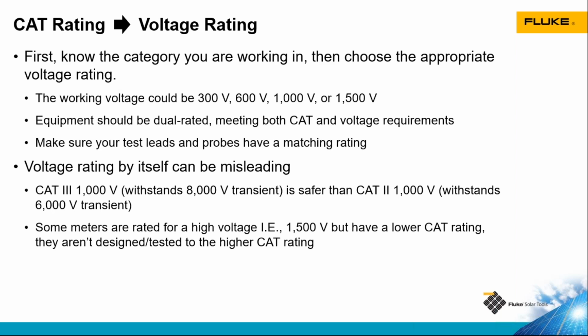And it's important to know that some meters on the market will be designed to test to a certain voltage, say 1,500 volts or even 2,000 volts. But when you look at the category and voltage rating, it's much less. I've seen 2,000 volt test tools that have only a category 3 1,000 volt or even category 3 600 volt rating. So when you're looking at test tools, make sure that the voltage it's marketed to test to also has the actual category and voltage listing to that level.